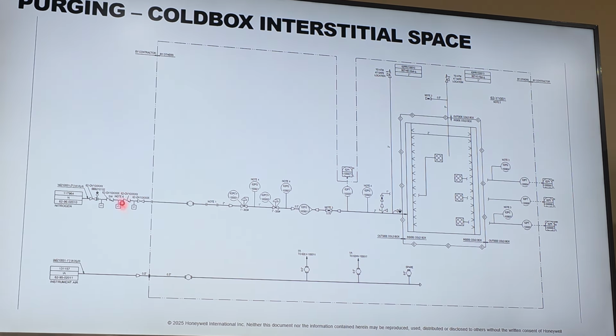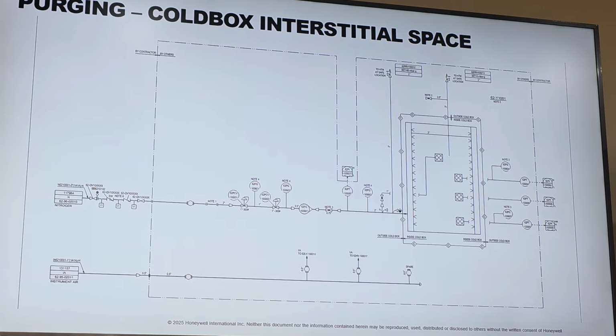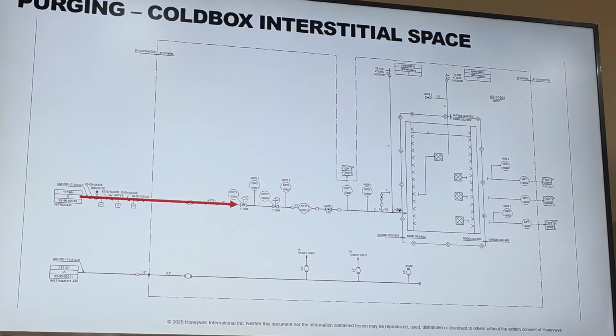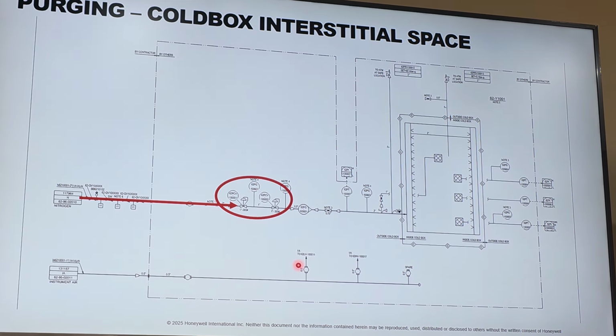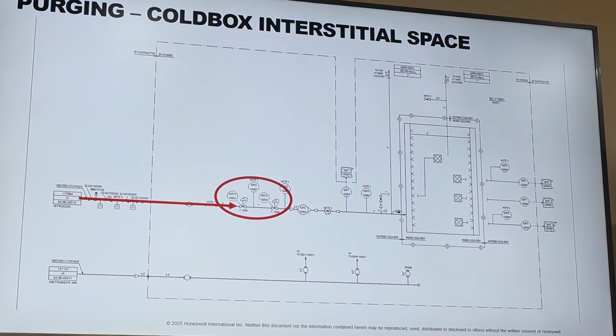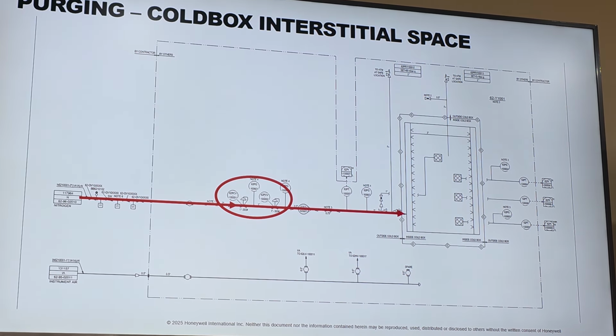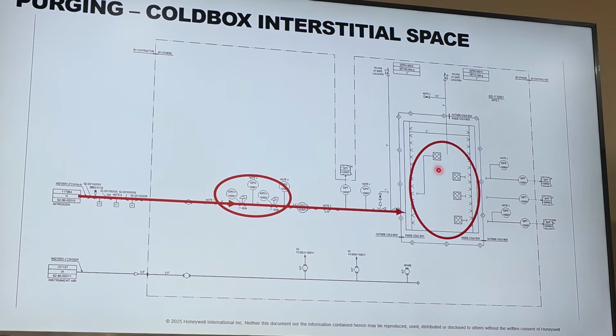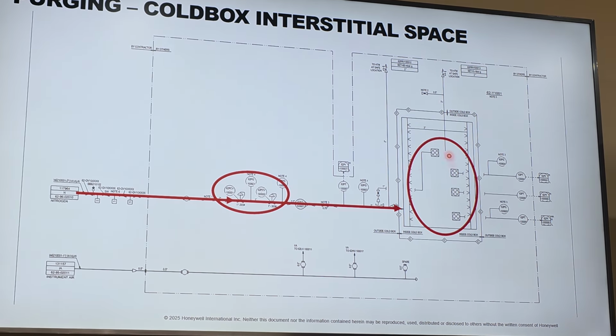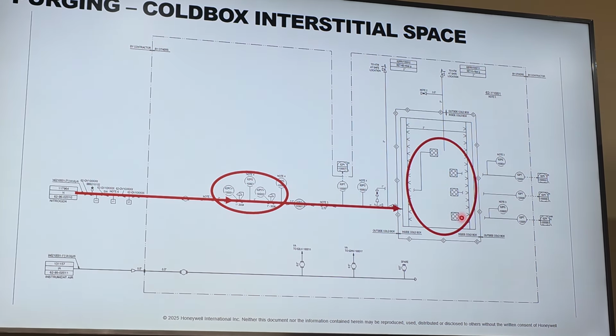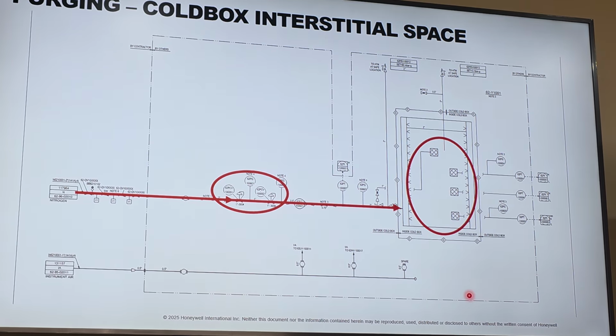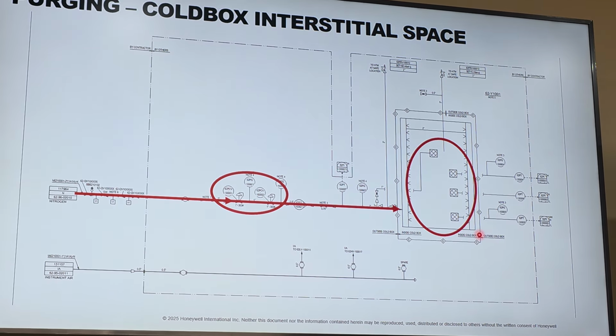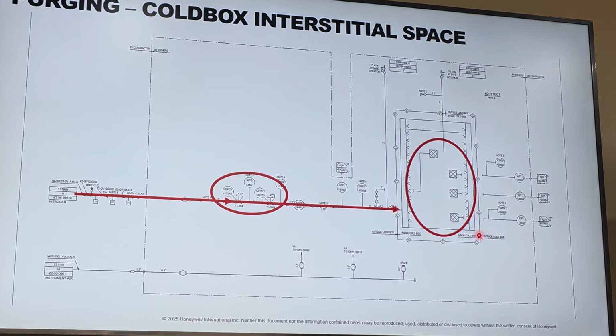Okay, so about purging the cold box. Same thing as before. You start the purge into the cold box. You have a pressure control valve to let down the pressure from your utility nitrogen system. It goes into the cold box. It gets dispersed through these, basically they're like sprayer bars with screens on them to protect them from being plugged. The nitrogen migrates through the insulation and out the top. No different than the nitrogen cold box. Leave it on, never shut it off, unless you're going to be down for months.